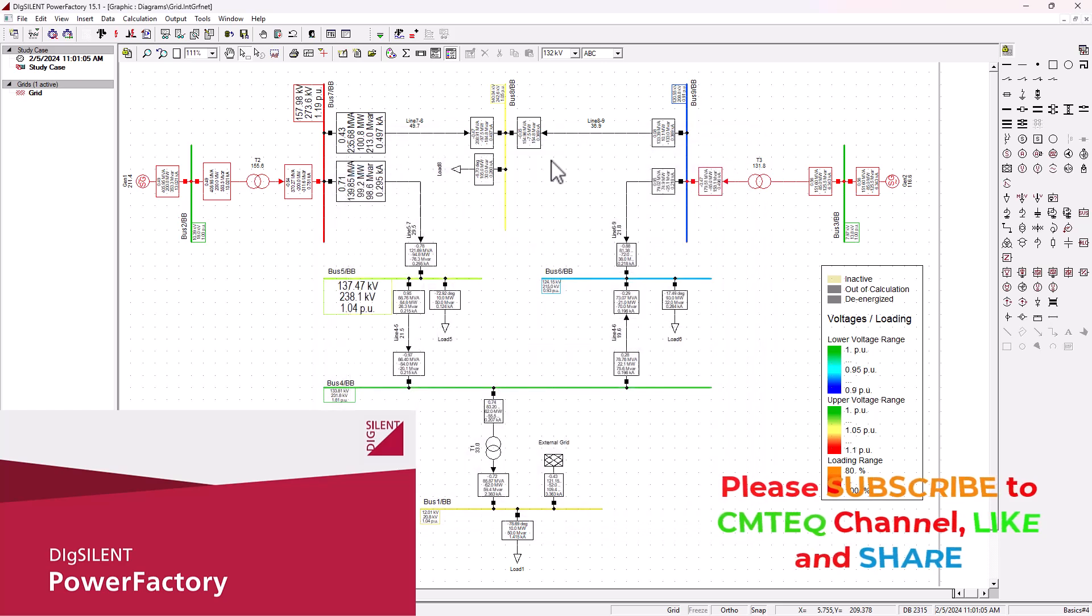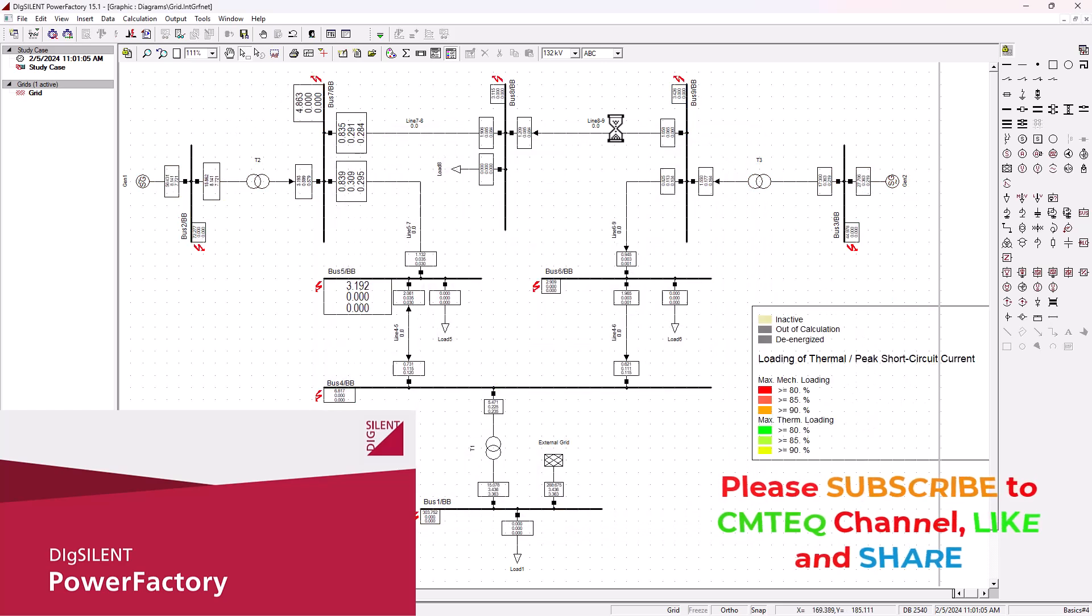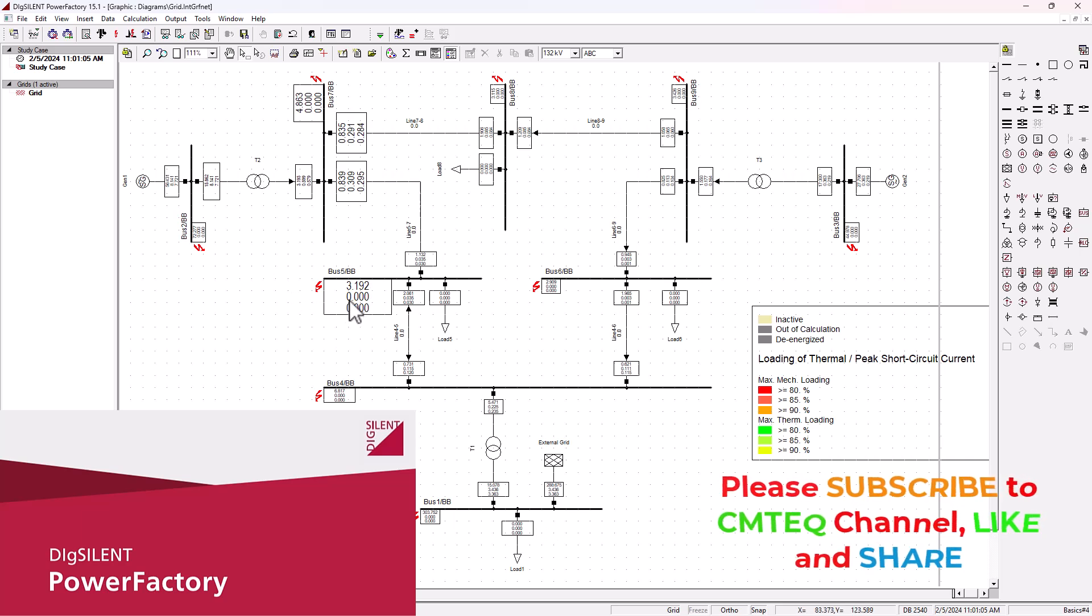When you click on execute, it will basically execute the short circuit on each one of these busbars here, so you will exactly know how much short circuit current will be present on each one of the busbars. When I hover here, we can see that on phase A I've got about 303.7 kiloamps of short circuit current on this busbar. This external grid is actually defined as the slack bus, basically the controlling grid.